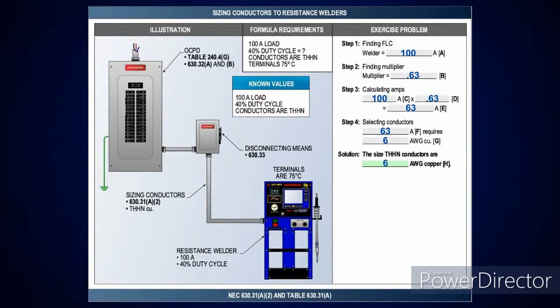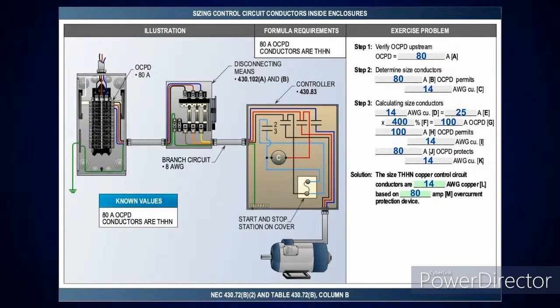And then this is just a clarification of what we looked at last week when we were dealing with these type of controllers. And I was saying, this is a start and stop station on the cover, and it's inside the controller. So that means it's in free air. Okay. So when you go down and look at the notes and you look at table 430.72(B) column B, it's going to tell you in the note that you're going to be looking at table 310.17.